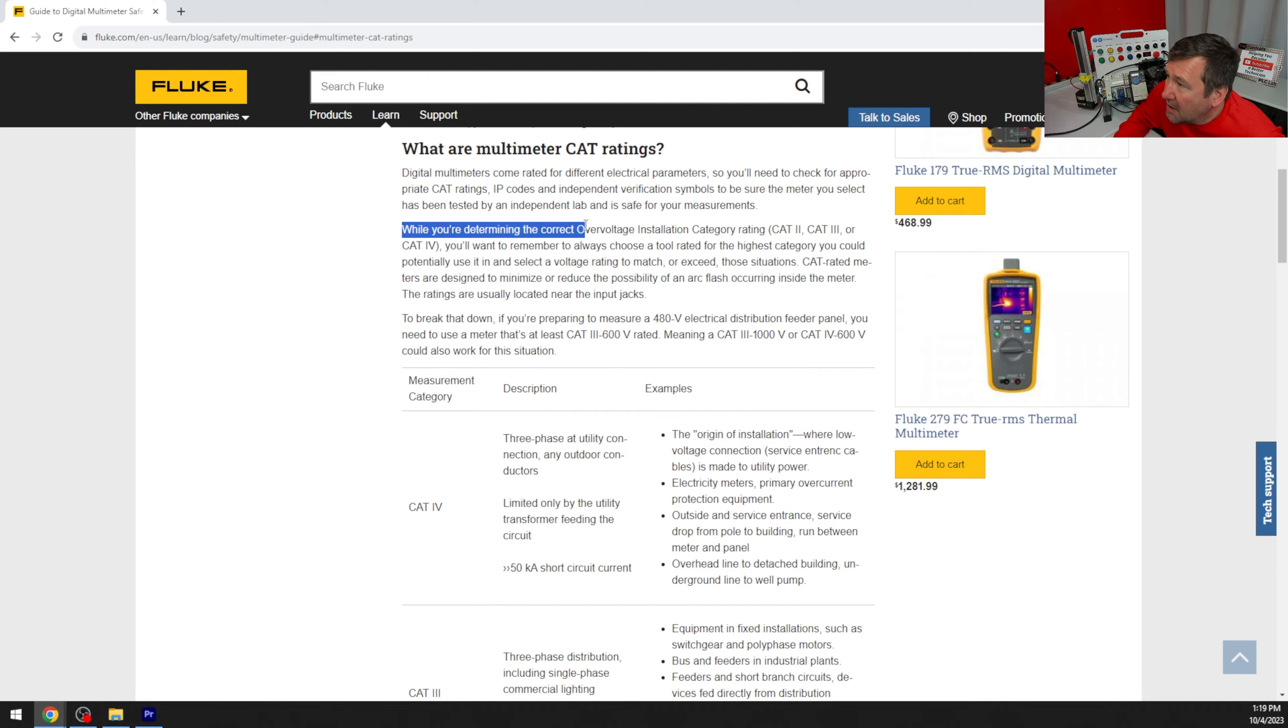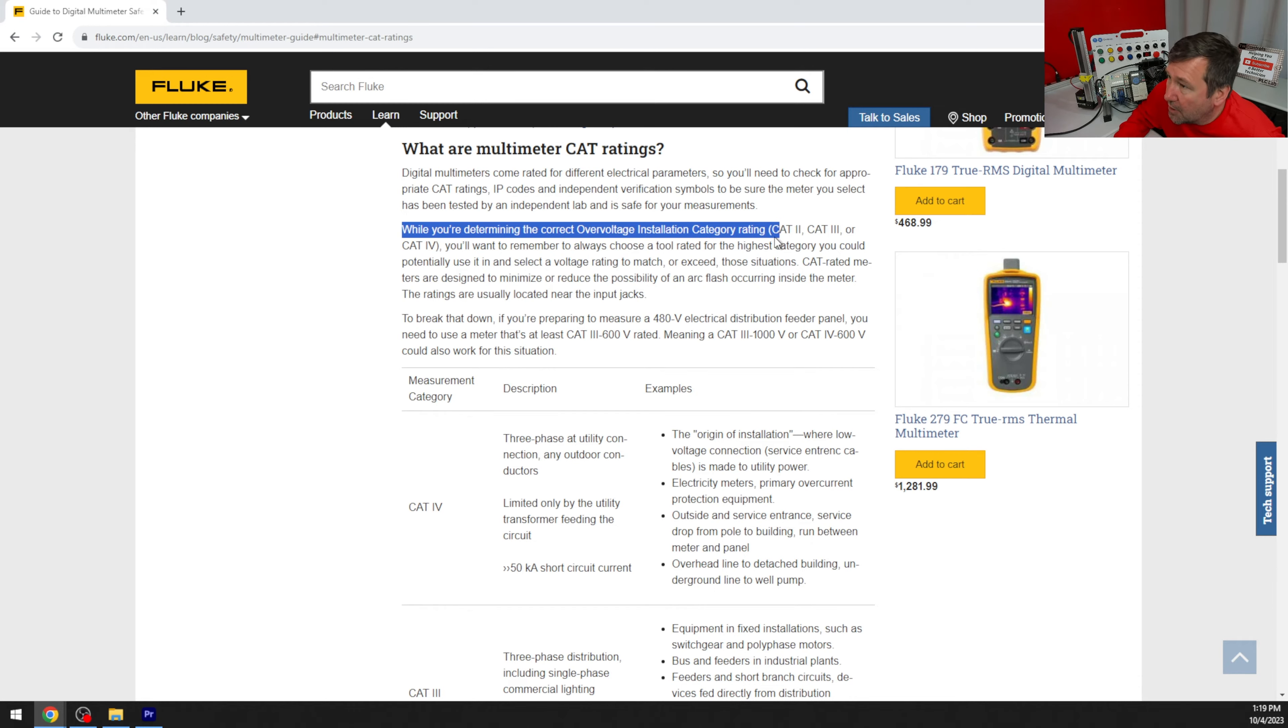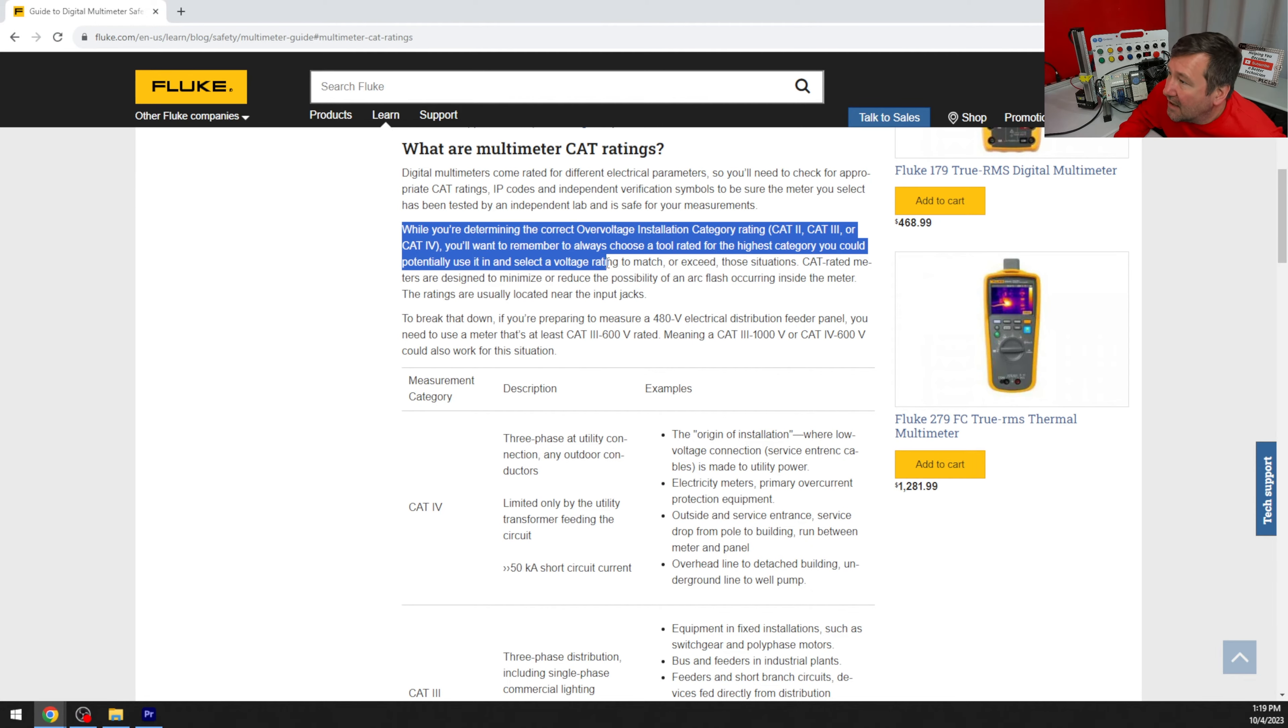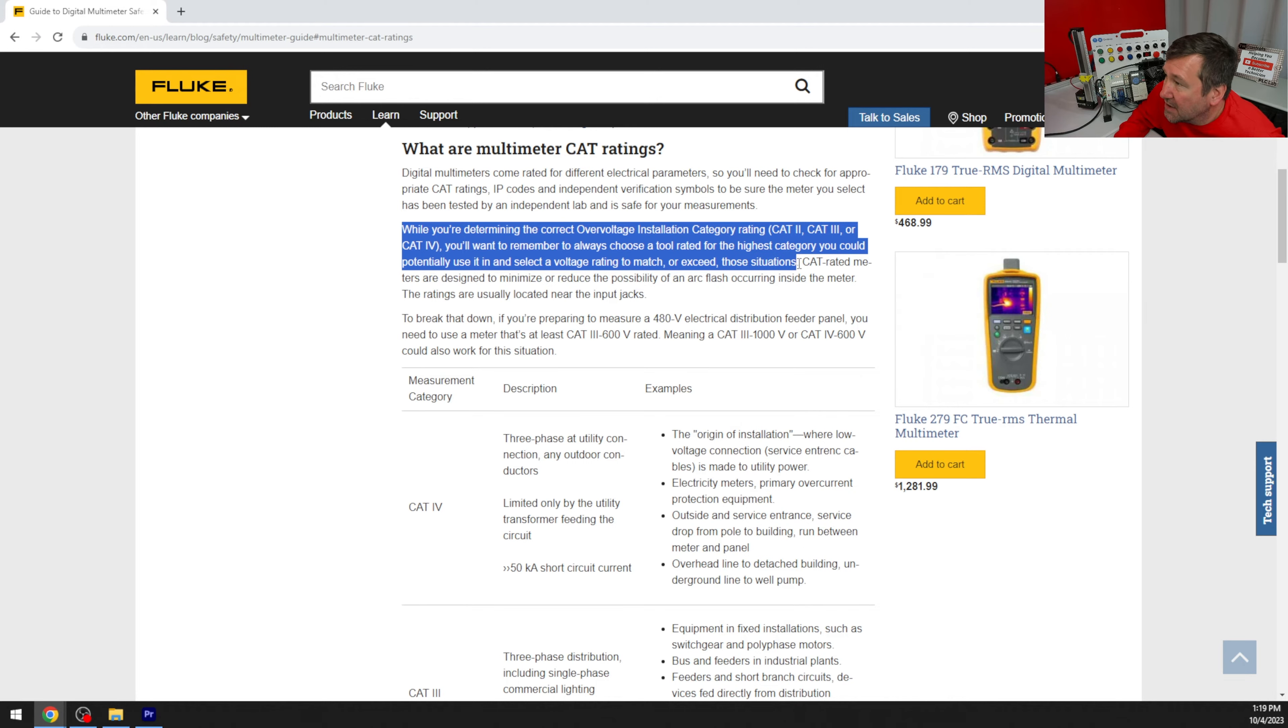While you're determining the overvoltage installation category, which is cat 2, 3, or 4, you'll want to remember to always choose the tool rated for the highest category you could potentially use it in and select a voltage rating to match or exceed those situations.